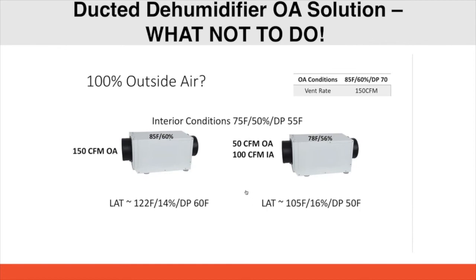And this unit would be a 70 pint unit, which would be 150 CFM of outdoor air that you're delivering into the AC system, and we're not removing any of that water. Once the dehumidifier does start removing water, it is generating heat, and it's the same scenario as we just talked about. This is being delivered into the AC system. We're going to heat up the coils on that AC system and reduce the latent removal. We do not recommend this install.